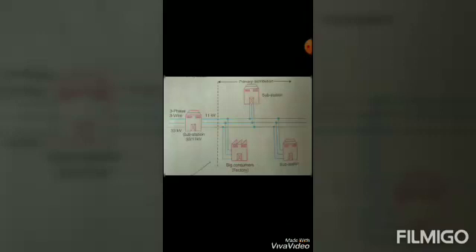Here we can see the three-phase three-wire system which is connected to the substation. The typical primary distribution system is shown in the figure. In this, the electric power from the generating station is transmitted at high voltage to the substation, that is a substation of 33 kV to 11 kV with the help of a step down transformer. This generating station power is transmitted at high voltage to the substation located near the city.